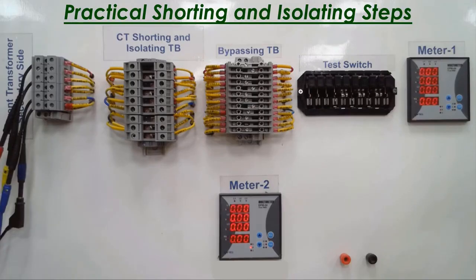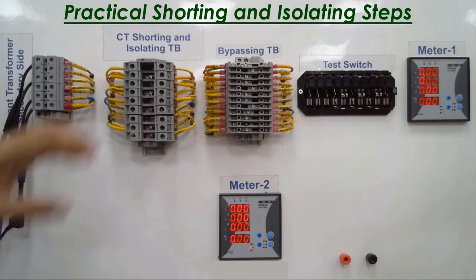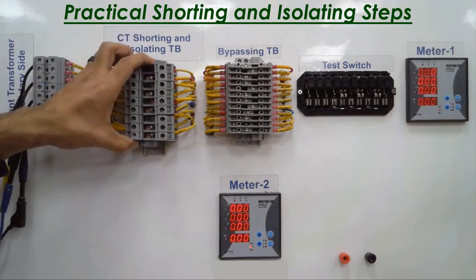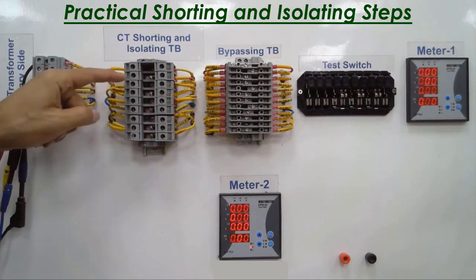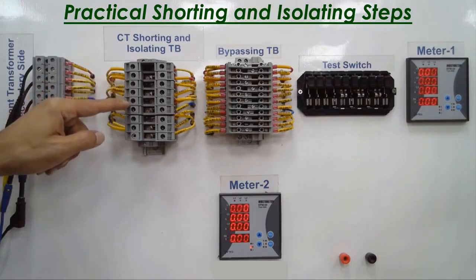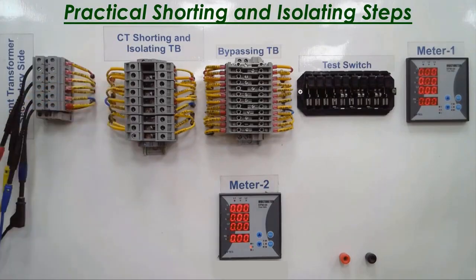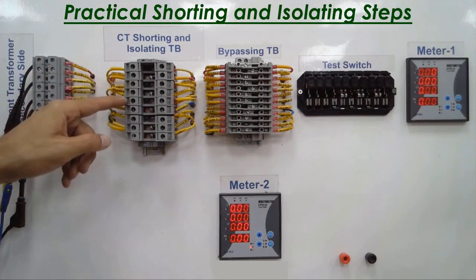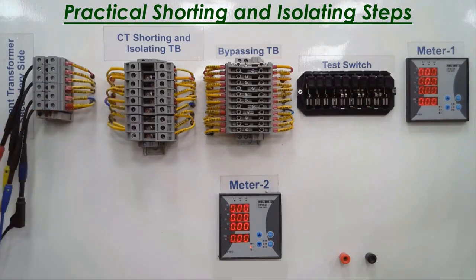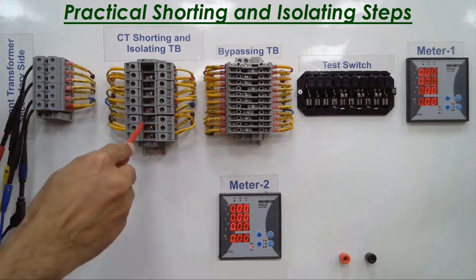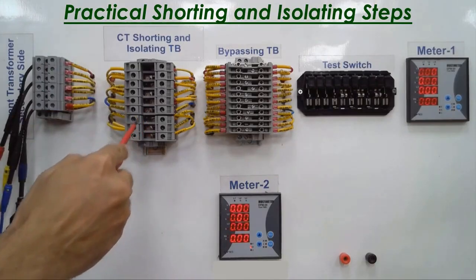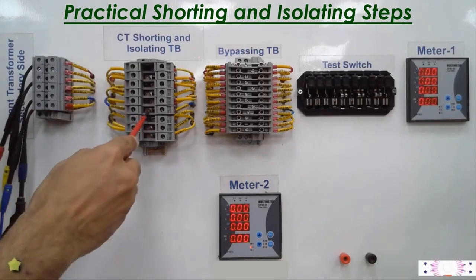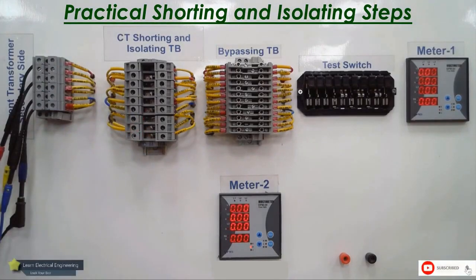But before I inject into my circuit, I need to ensure that my circuit is in the normal position. So of course, here I have the shorting and isolating TBs. Their normal position is that terminals 2, 4, 6, and 8 are closed, and terminals 1, 3, 5, and 7 are open. The idea of the open position is that you will find the link on your right side, and for the closed position, you will find the link on your left side. As for the finger type test switch, you will find all the fingers closed.